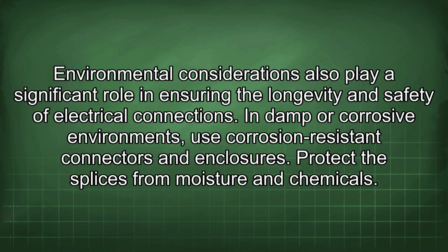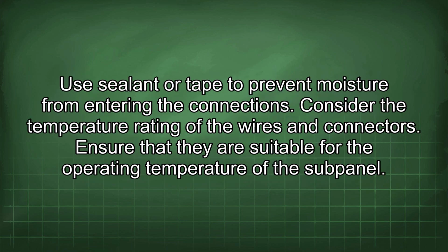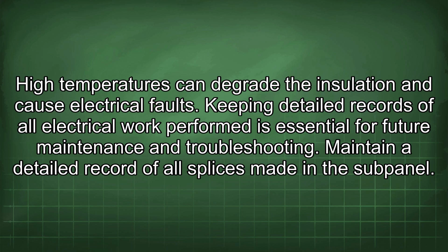Environmental considerations also play a significant role in ensuring the longevity and safety of electrical connections. In damp or corrosive environments, use corrosion-resistant connectors and enclosures. Protect the splices from moisture and chemicals. Use sealant or tape to prevent moisture from entering the connections. Consider the temperature rating of the wires and connectors. Ensure that they are suitable for the operating temperature of the subpanel. High temperatures can degrade the insulation and cause electrical faults.